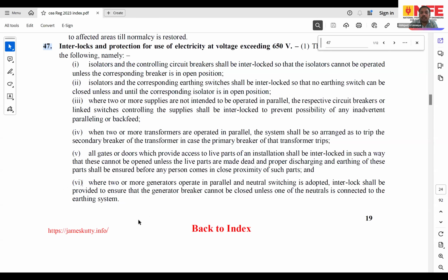However, another problem that arises is that in case these neutrals are separately earthed and one of the transformer neutrals gets disconnected from earth, there could be dangerous overvoltages if the reference of the transformer neutral doesn't get established. And also, in case of multiple neutrals, let's say you have multiple transformers, the standard practice would be to bring all the neutrals to a common bus and then earth that common bus. And then maybe switch that neutral through a neutral contactor in case a switch neutral is needed.